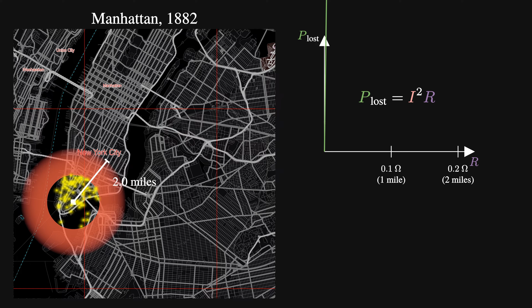Well, to light up a neighborhood of Edison's size, which we'll say is about 500 lamps, you need about 40,000 watts of power. However, these lamps operate at around 110 volts. If the voltage is much higher than this, they'll just explode. As the power is equal to the current times the voltage, the current needed is about 364 amps. This is absolutely huge. Even through 0.1 ohms of resistance, the power dissipated at this current is 13,000 watts. That's already a third of the power generated, and this is only for a few street lamps. If the power needed increases, the current scales rapidly, and the losses just get ridiculous.